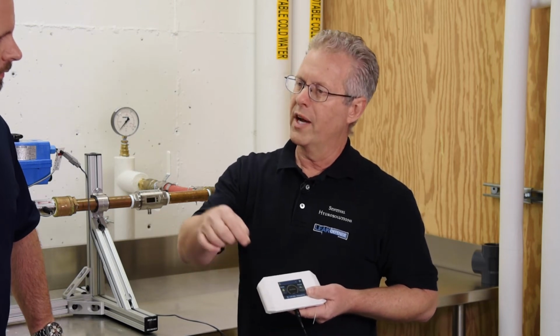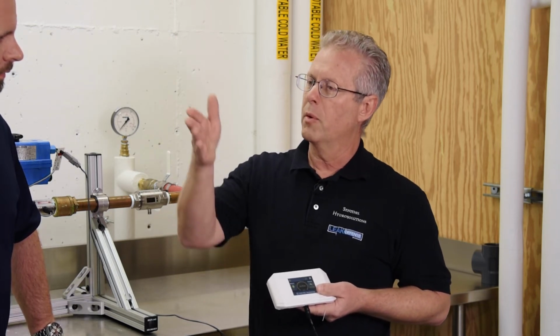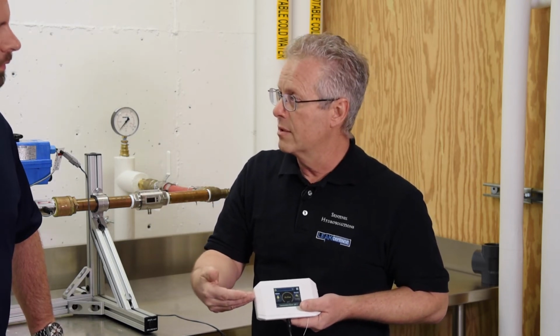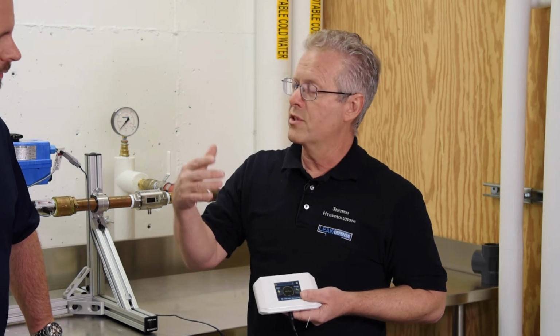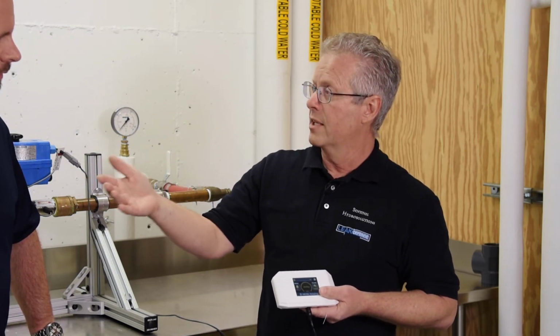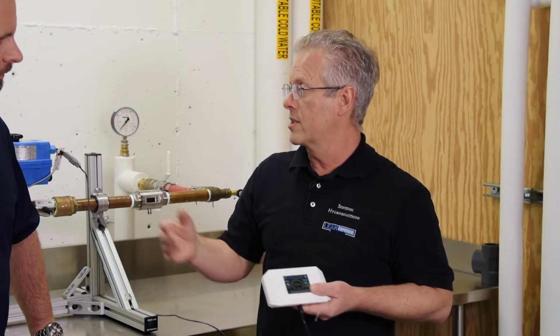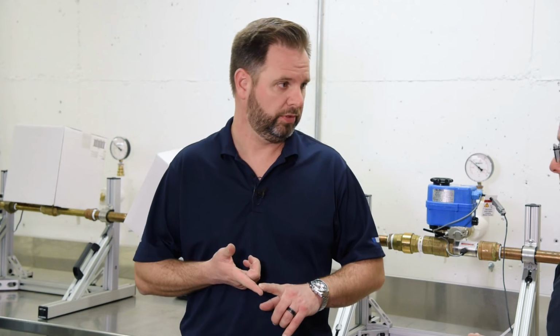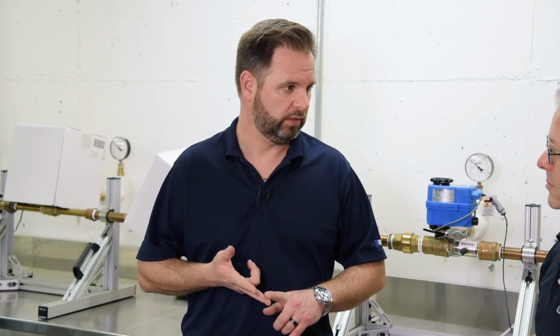So we can provide an input to that, so remotely, if there's a human being that's taking those calls, it will show up as leak defense valve closed. Typically they're given a series of people to contact in the event they get alarmed. So that's another way to communicate. You can hook it up to a third-party alarm company or a smart building management system as well. So that's just another safety layer that the other guys might not have.